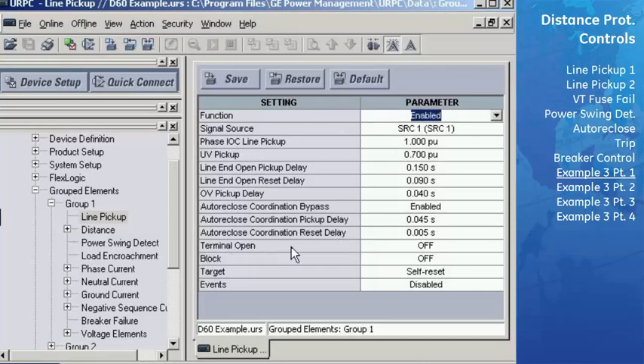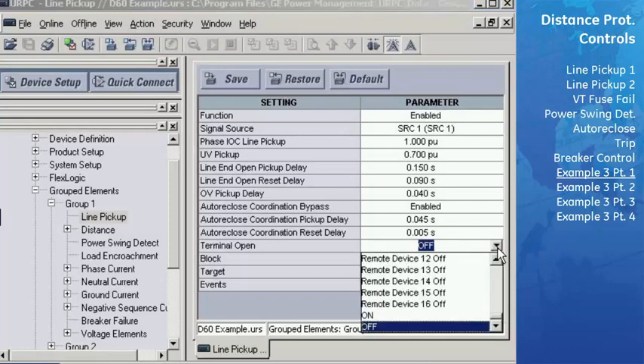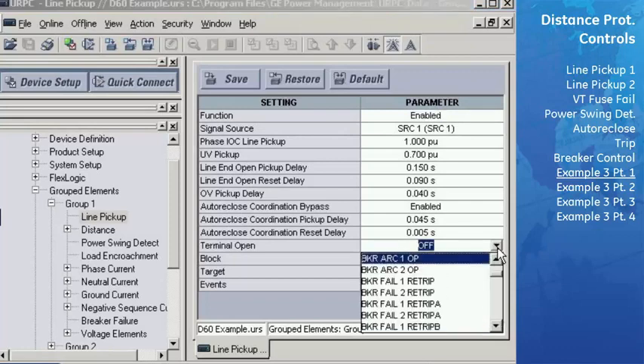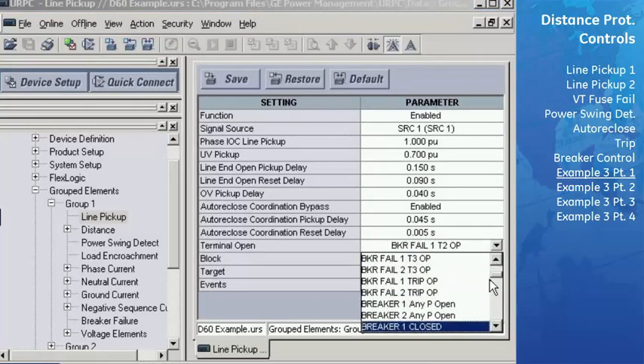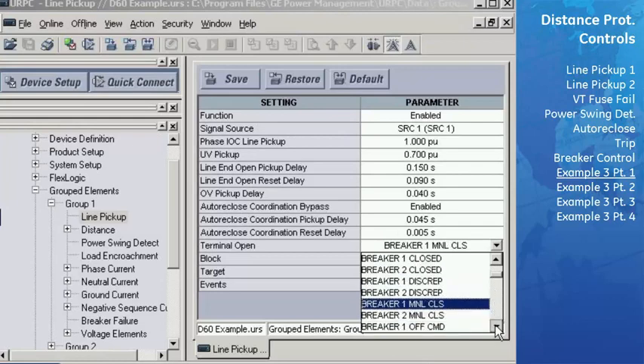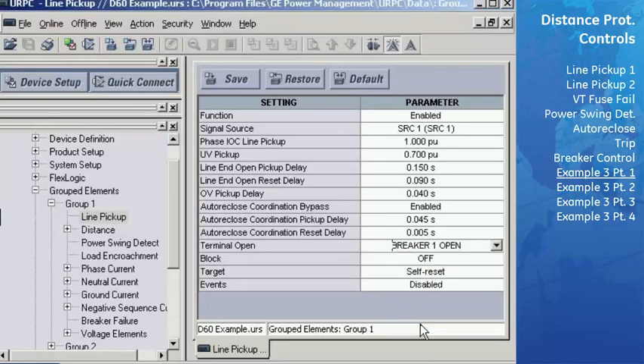Change the terminal open field to flex logic signal breaker 1 open, which is the signal from the breaker control logic. This signal indicates the breaker is open from the breaker 52A contact. This will be set a little later in the breaker control menu. The block function won't be used for this example and can be left as off. Change the target to latched and the events to enabled to have the operating of this element appear in the event report.